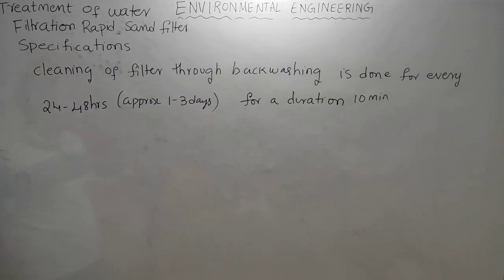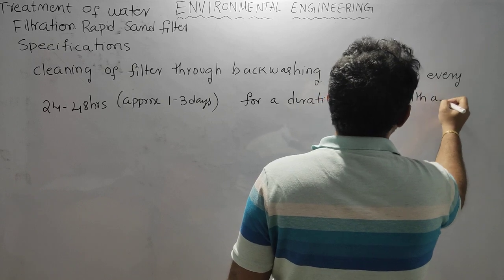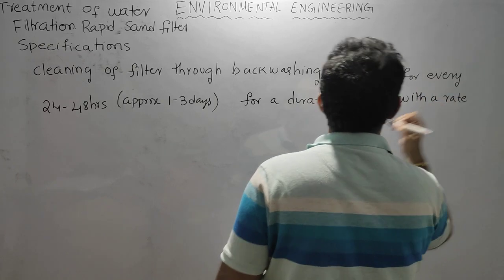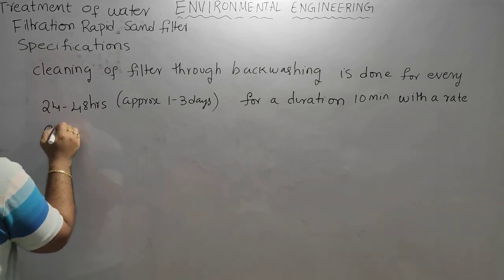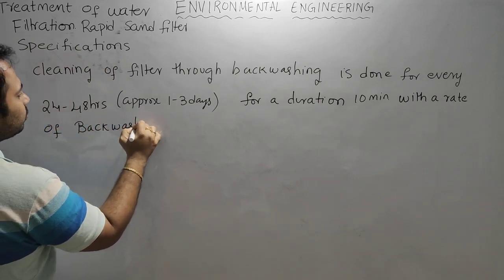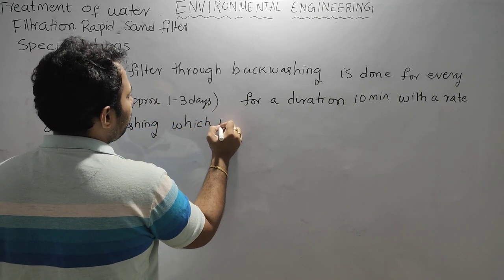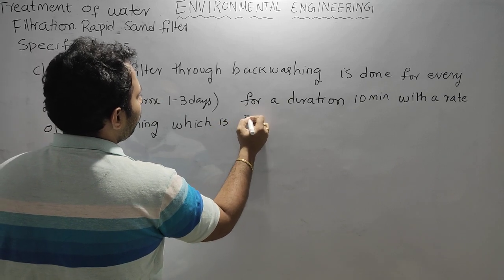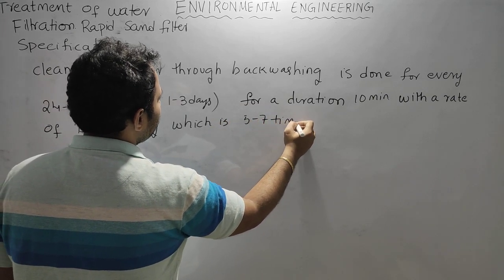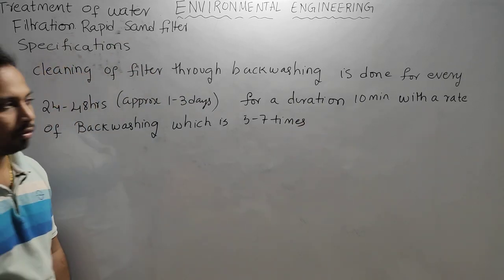With a backwashing velocity of 5 to 7 times the rate of filtration. The rate of backwashing is 5 to 7 times the rate of filtration.